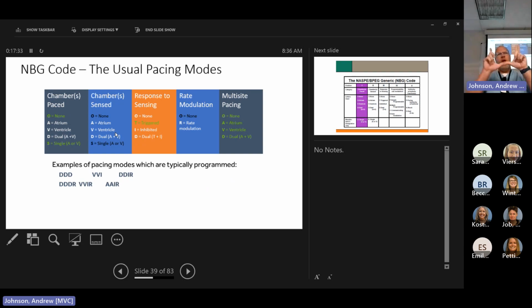If we're not pacing, we have a window, and every pacemaker has a window. When we say 60 beats a minute, that's 1,000 milliseconds. After 1,000 milliseconds, that's my window. If I didn't see anything at 1,000 milliseconds, I provide a beat. If I see something in this 1,000 milliseconds, that is a sensed beat, so I move over my window.